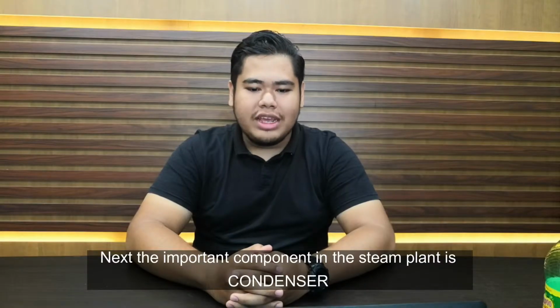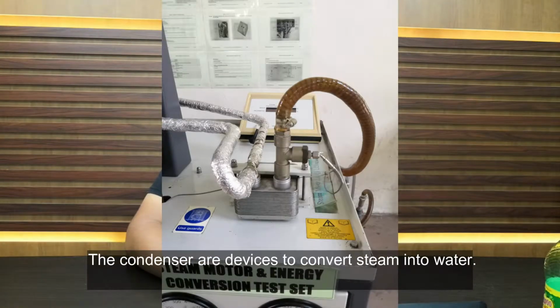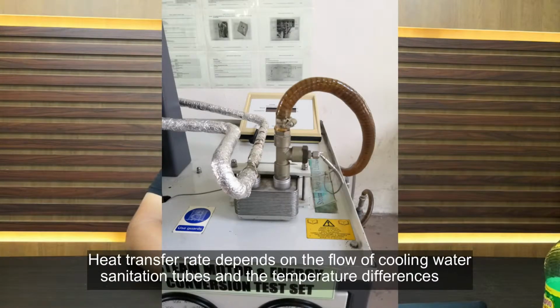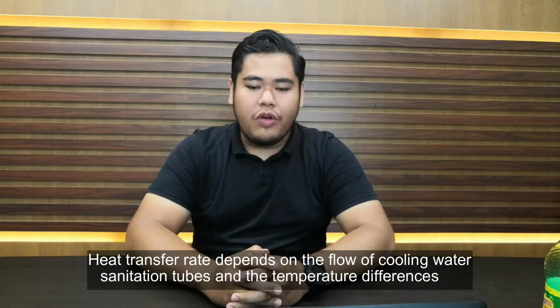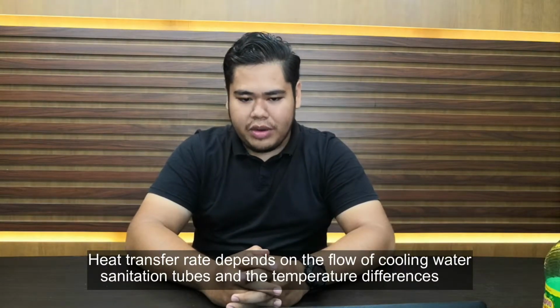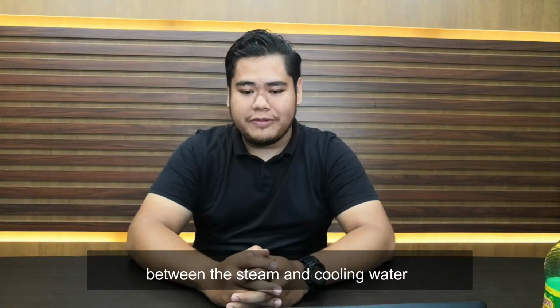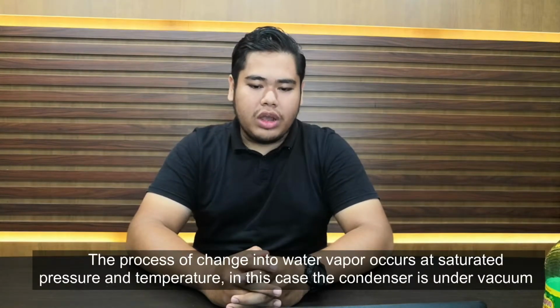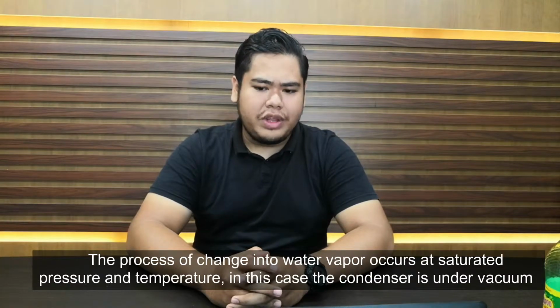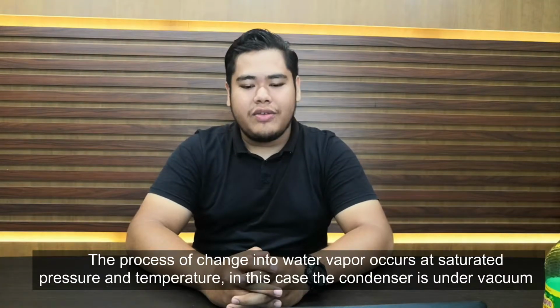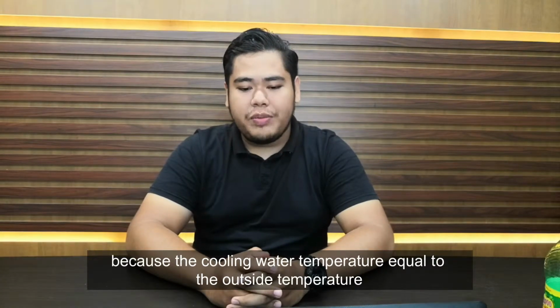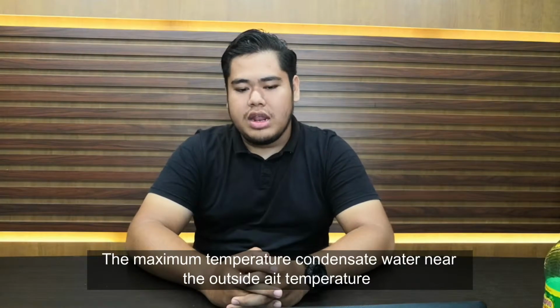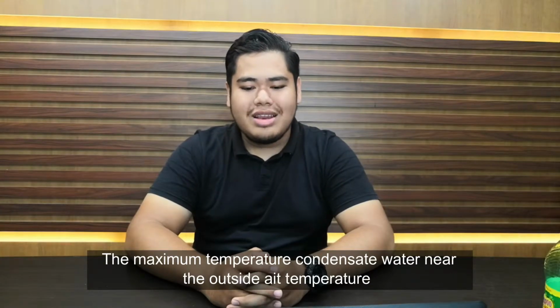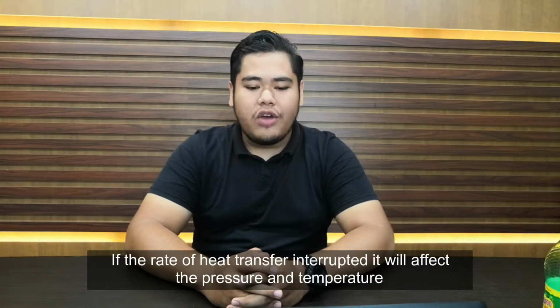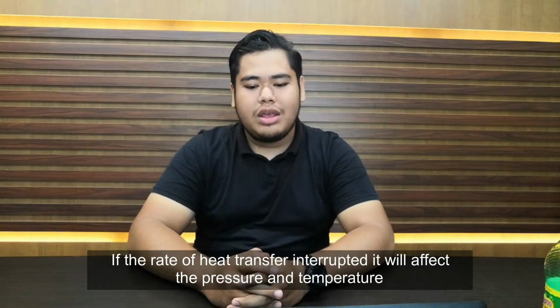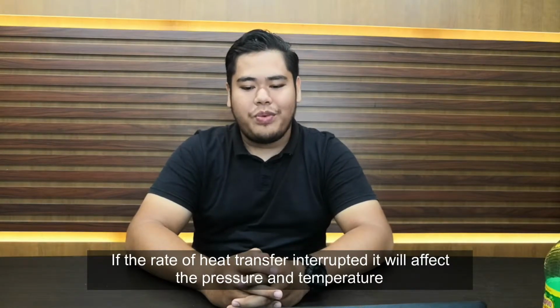Next, the important component in the steam plant is the condenser. The condenser is a device to convert steam into water. Heat transfer rate depends on the flow of cooling water, the tube condition, and the temperature difference between the steam and cooling water. The process of change into water occurs at saturated pressure and temperature. In this case, the condenser is under vacuum because the cooling water temperature is equal to the outside temperature. The maximum temperature of condensate water is near the outside air temperature. If the rate of heat transfer is interrupted, it will affect the pressure and temperature.